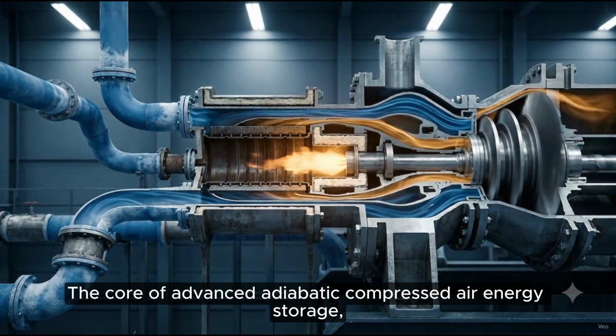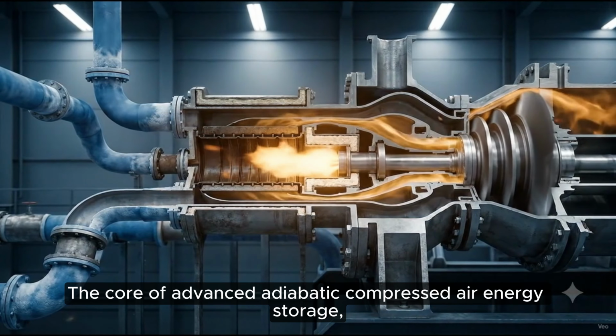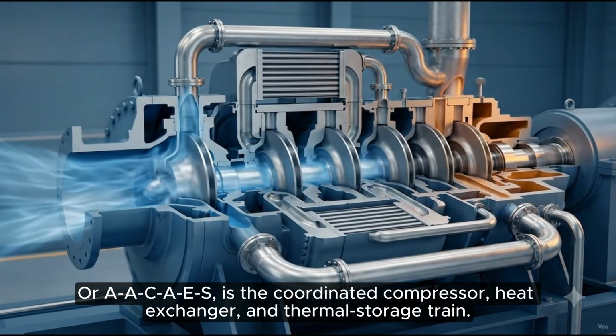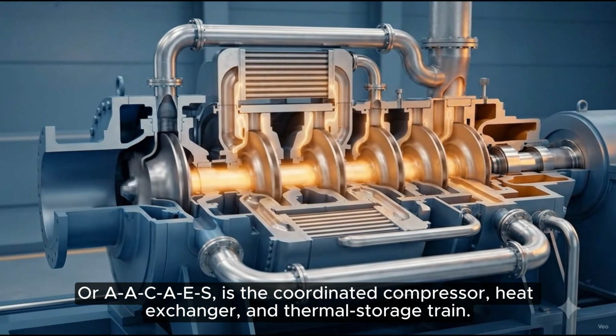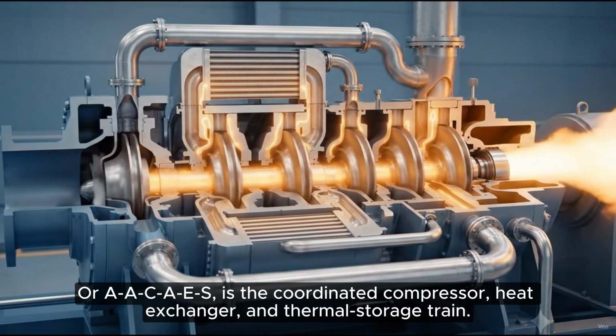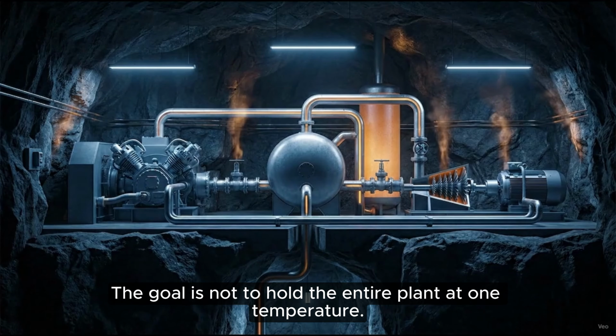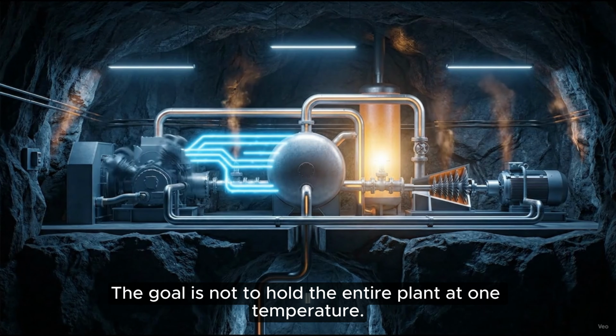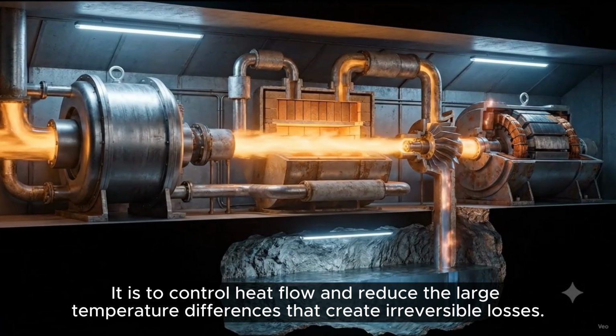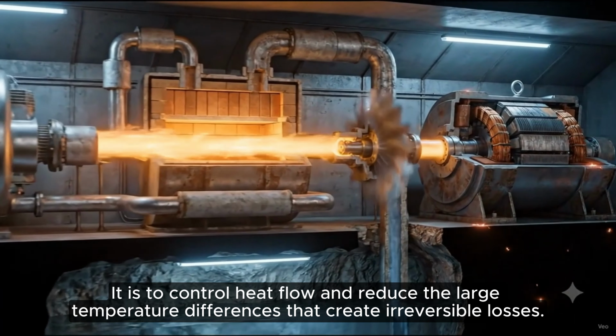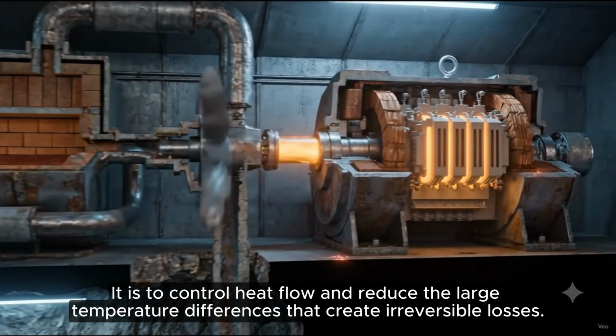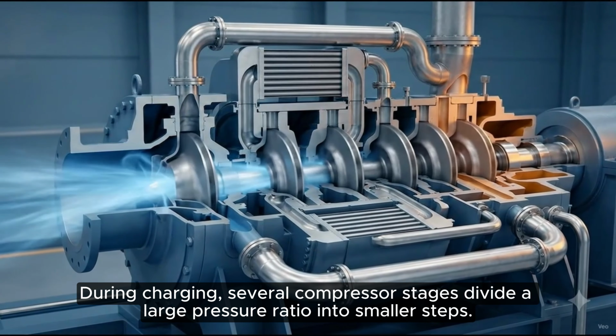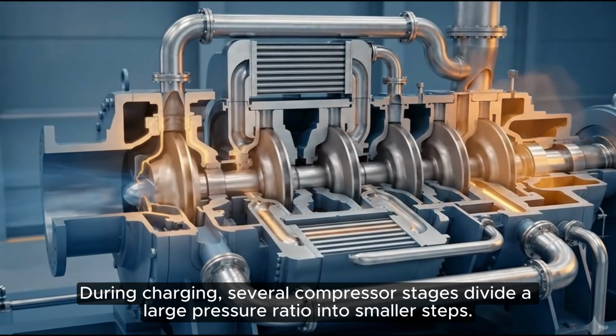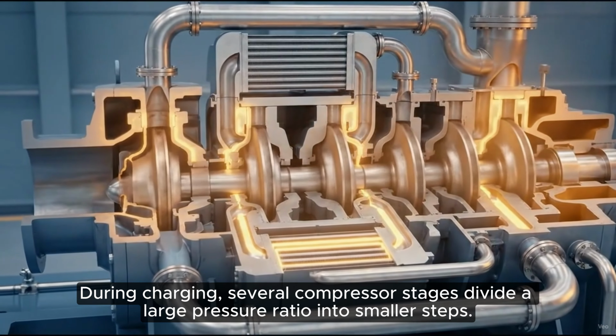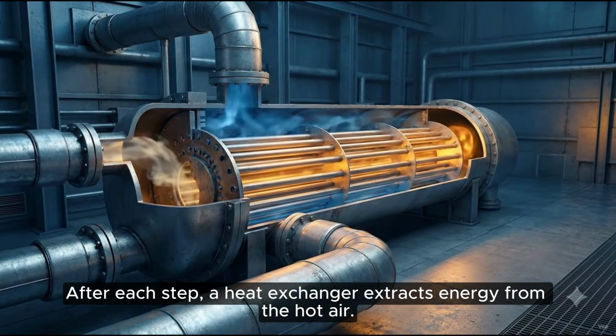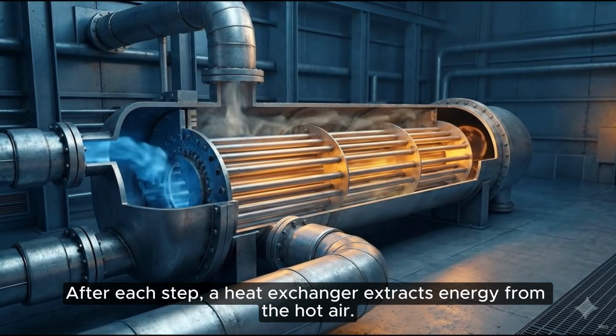The core of advanced adiabatic compressed air energy storage, or AA-CAES, is the coordinated compressor, heat exchanger, and thermal storage train. The goal is not to hold the entire plant at one temperature. It is to control heat flow and reduce the large temperature differences that create irreversible losses. During charging, several compressor stages divide a large pressure ratio into smaller steps. After each step, a heat exchanger extracts energy from the hot air.